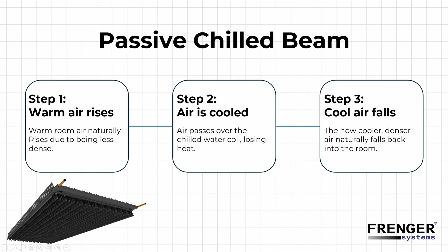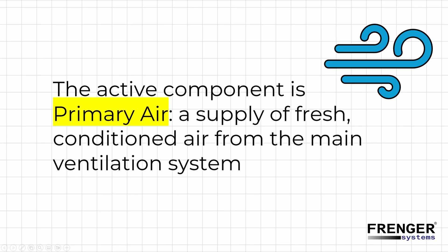All right, so if passive beams are that simple and elegant, you might be wondering, why do we even need an active version? Well, that's where we unlock a whole new level of performance and control. The key difference, the secret ingredient, is this one addition: primary air. An active chilled beam is hooked up to the building's main ventilation system, which feeds it a steady supply of fresh, conditioned air. And this air does more than just help us breathe. It's the catalyst that turbocharges the whole cooling process.